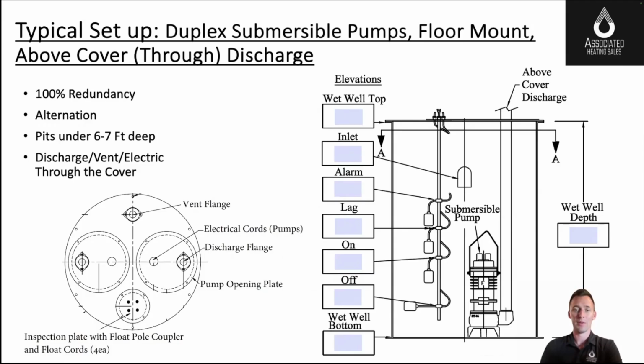We're going to talk about the drawings that you'll see for typically duplex sump pumps or duplex sewage pumps. When I say typically duplex, I mean that most of our systems are duplex because there's redundancy in these commercial buildings that allows the commercial building to continue to operate while one pump is down.